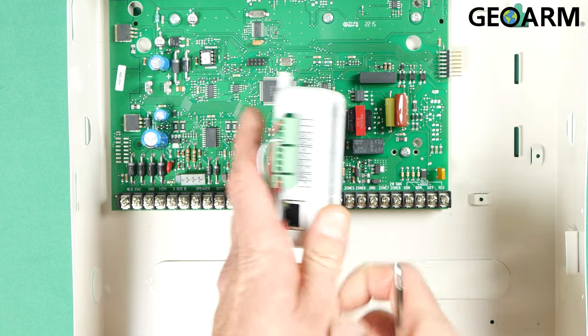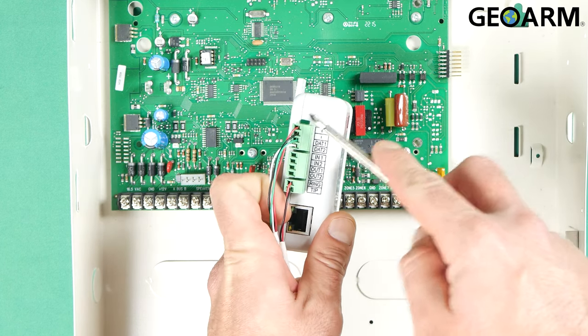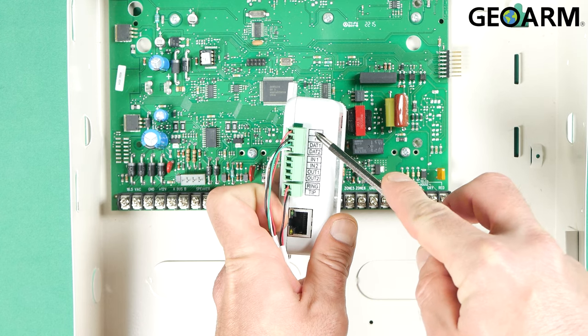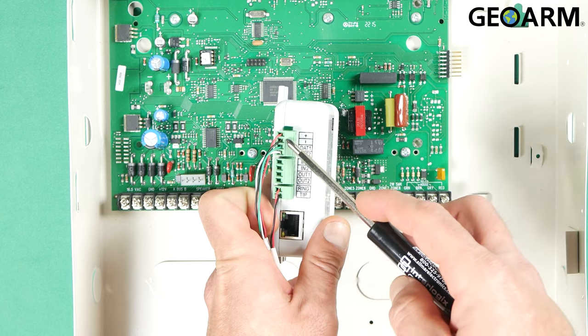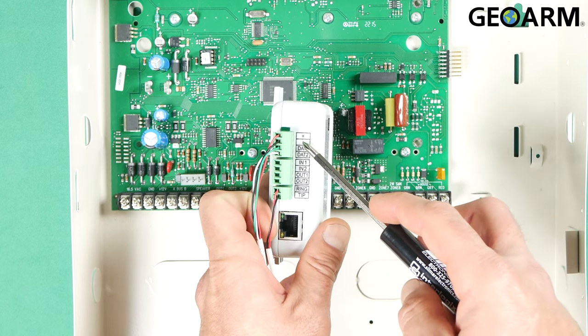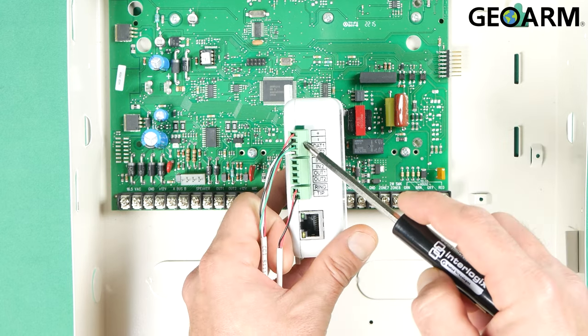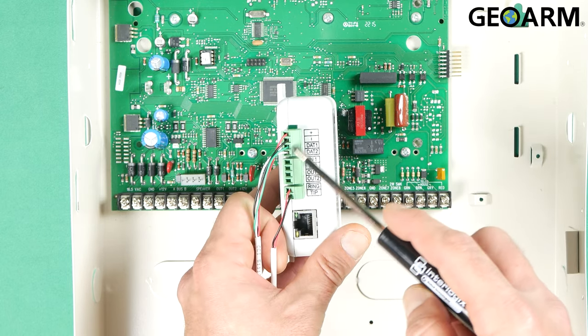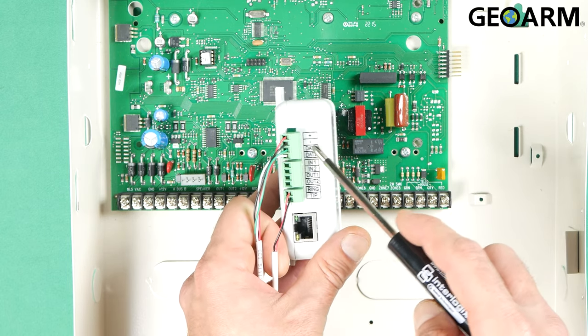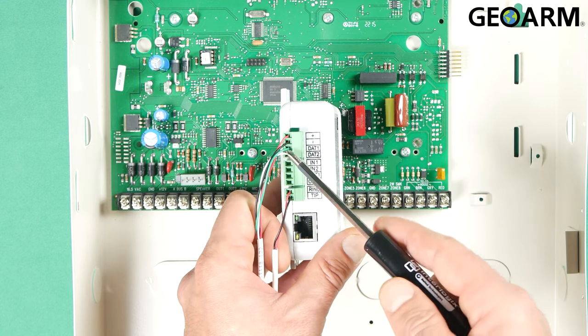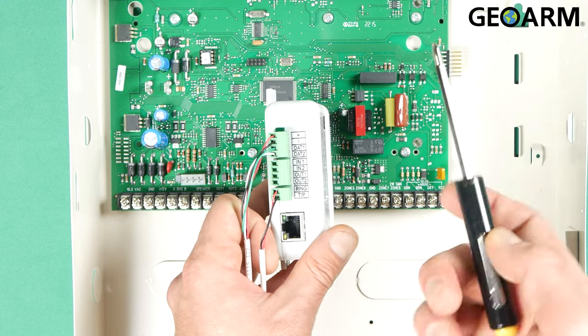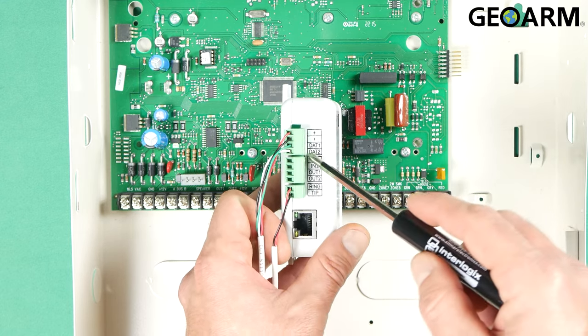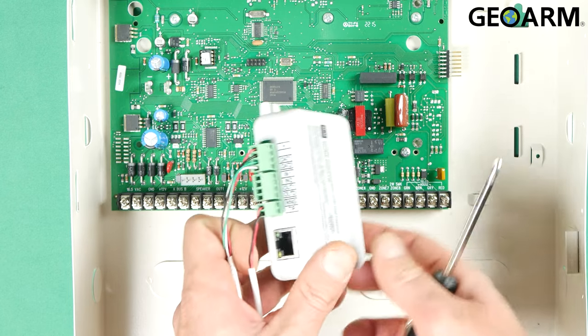So the first wire we'll go over here is the red wire. I've wired that to positive or plus. The black wire I've wired to minus or negative. My green wire I've wired to DAT1. And my white wire, or it could be yellow in your case for your 4 conductor, is going to DAT2.